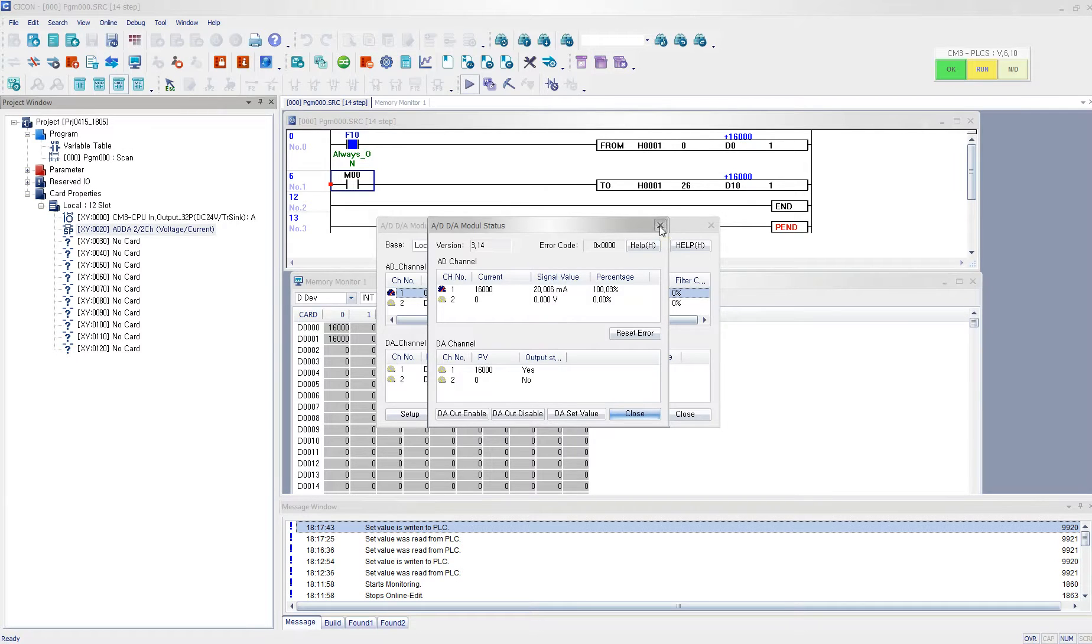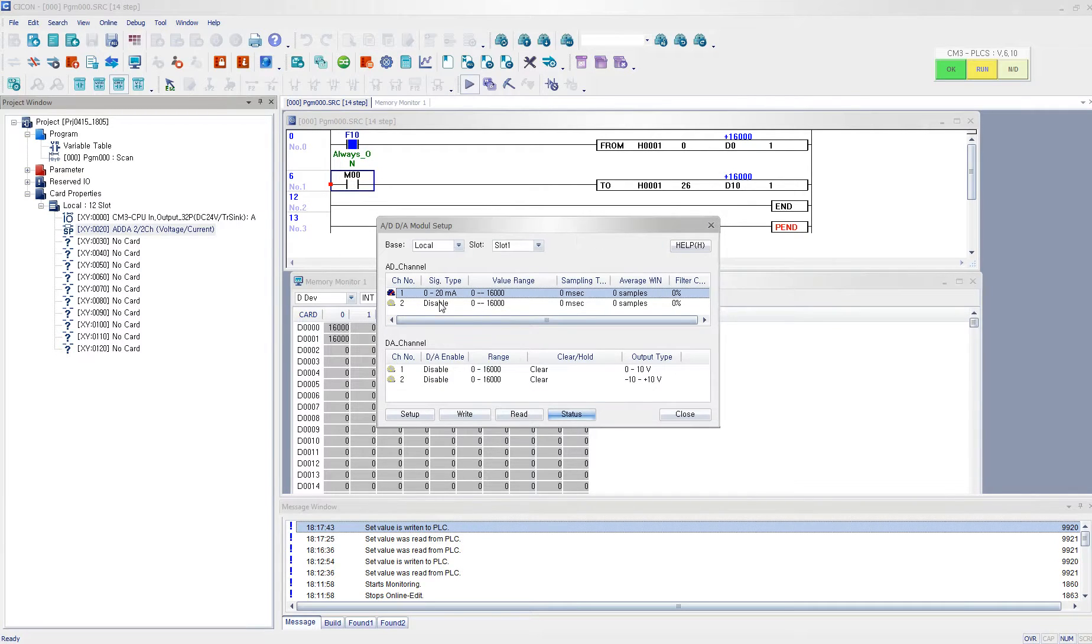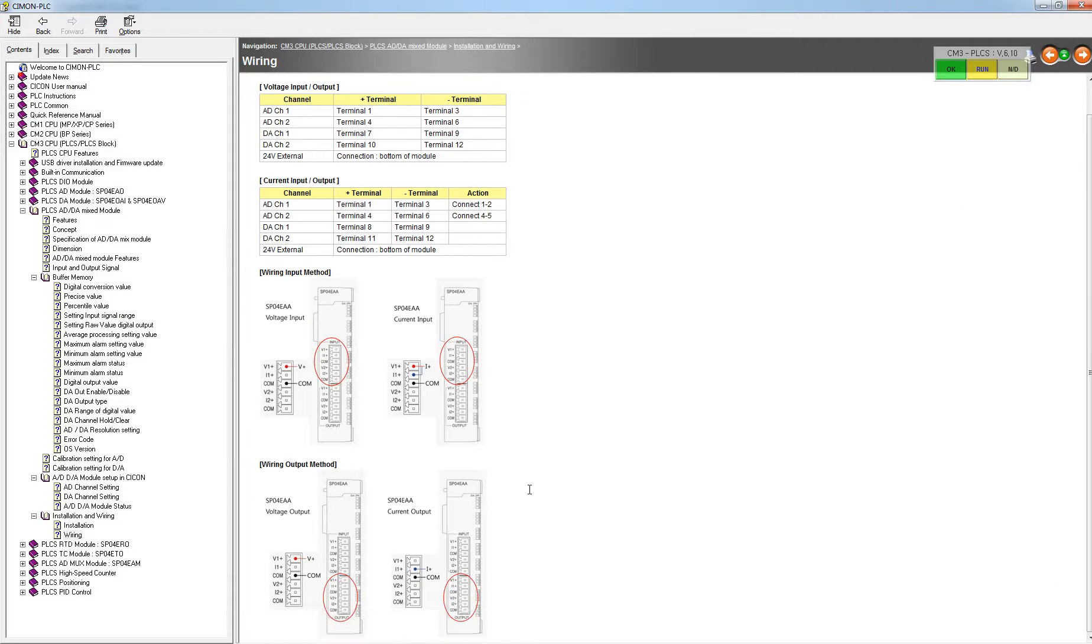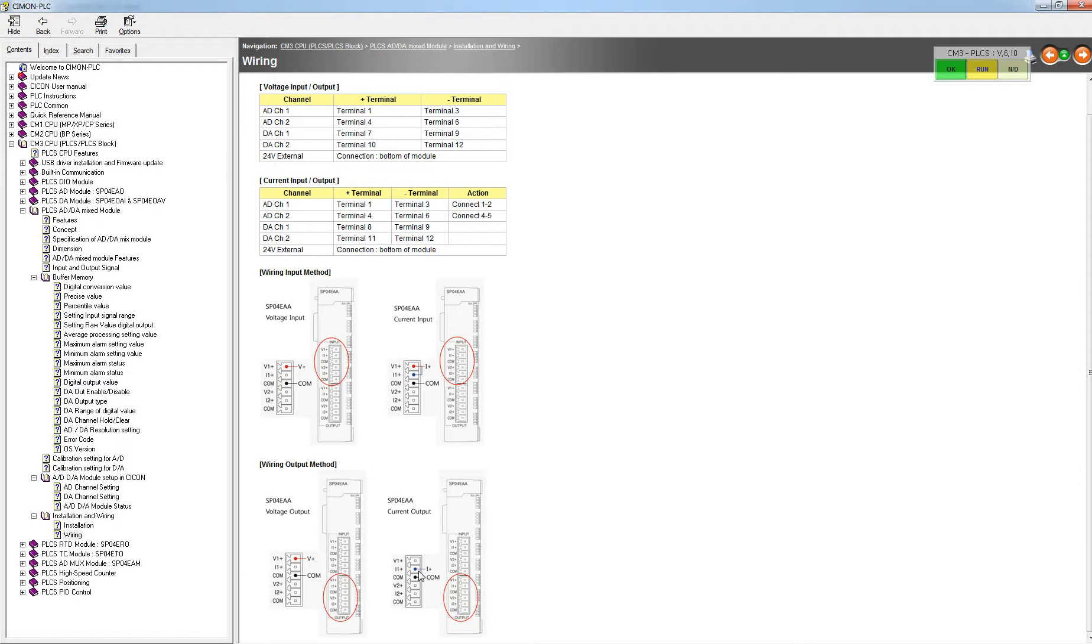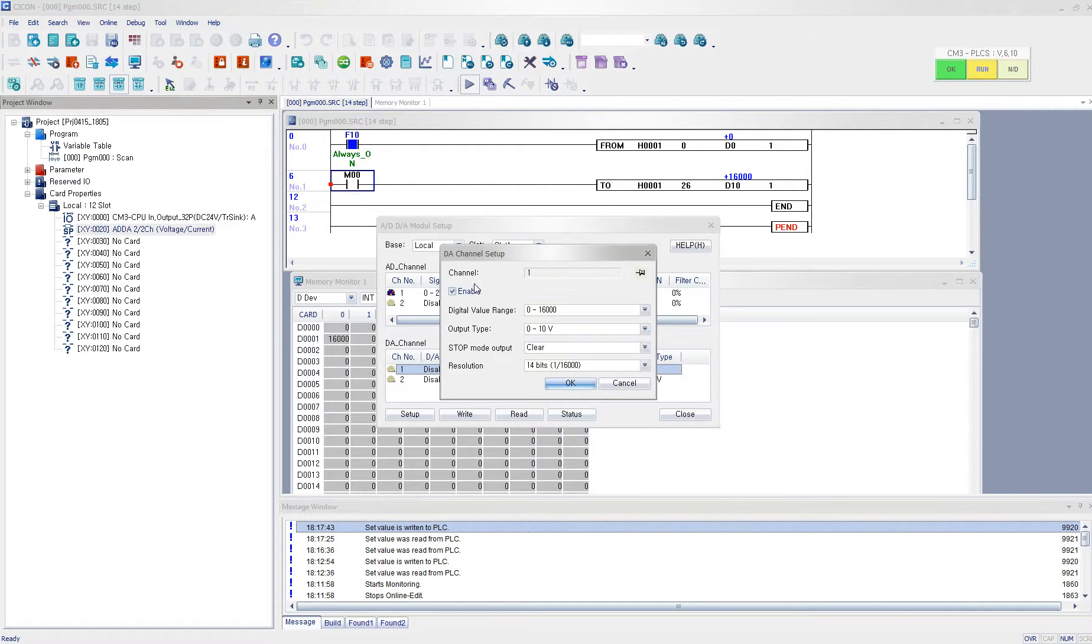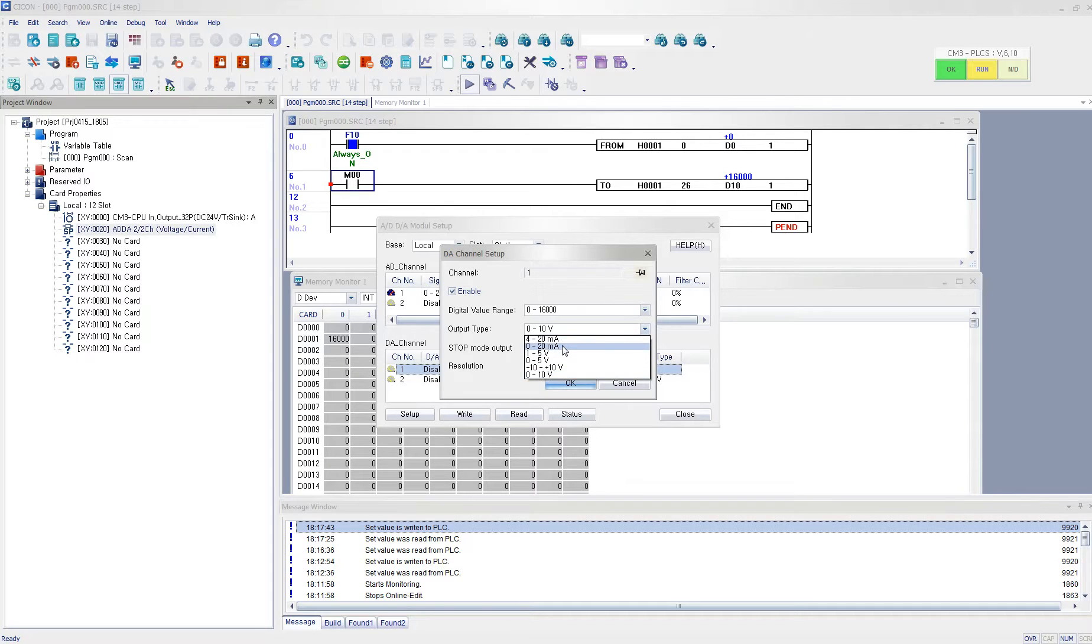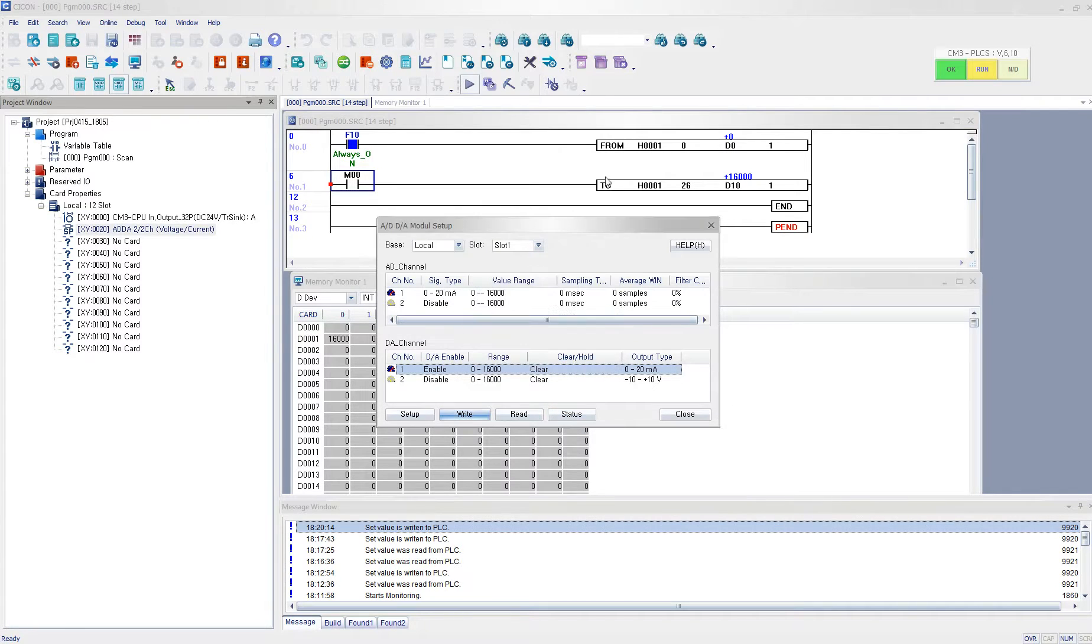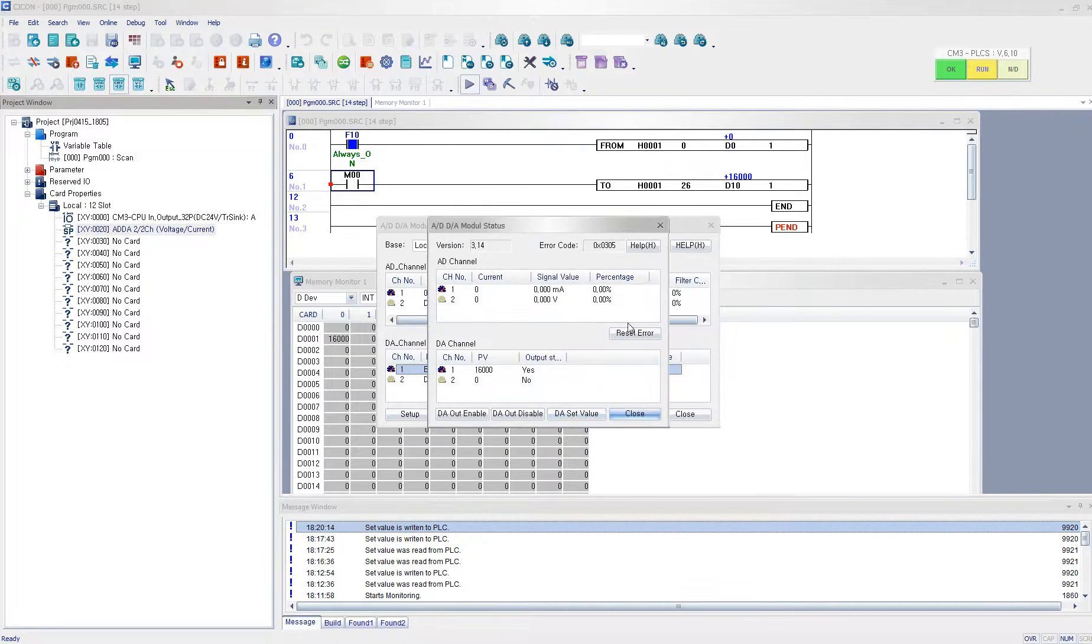And now I want to output this value in milliampere. And I refer to the wiring scheme. And since now I am going to output my current, I have wired the current here and I have wired the COM over here. Then I configure, I enable my DA channel, the first channel. And then I output type will be the current instead of voltage. And I write it, and I click status.